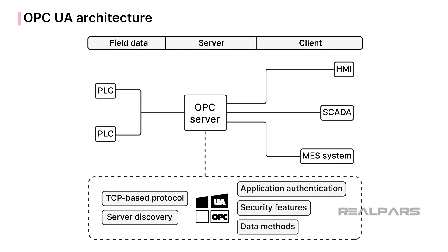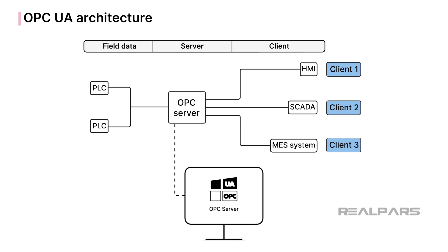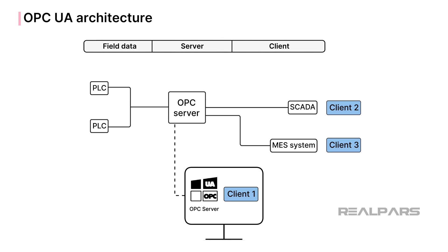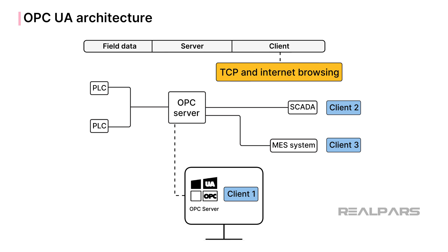The OPC UA-based software installation is made up of a binary TCP-based protocol, plus a method for allowing the OPC UA server to be discovered by other computer applications across the network. It also includes application authentication, other security features, and data methods to access devices such as PLCs. The OPC UA client software can be loaded on the same PC as the OPC UA server, on a different machine on the same network, or on a PC anywhere on the internet or in the cloud. Because the OPC UA client uses TCP and internet browsing protocols to connect to the OPC UA server, the OPC UA client can literally be located anywhere.